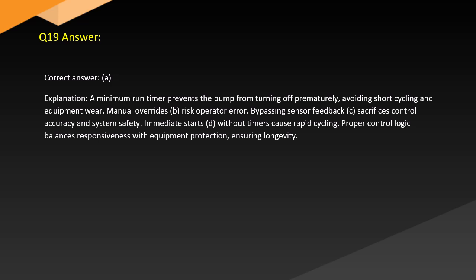A minimum run timer prevents the pump from turning off prematurely, avoiding short cycling and equipment wear. Manual overrides, B, risk operator error. Bypassing sensor feedback, C, sacrifices control accuracy and system safety. Immediate starts, D, without timers cause rapid cycling. Proper control logic balances responsiveness with equipment protection, ensuring longevity.